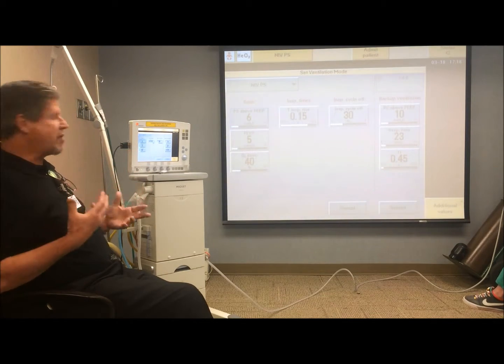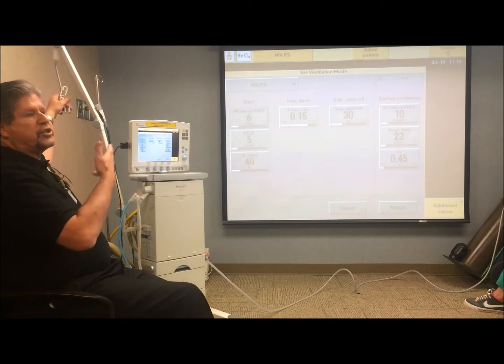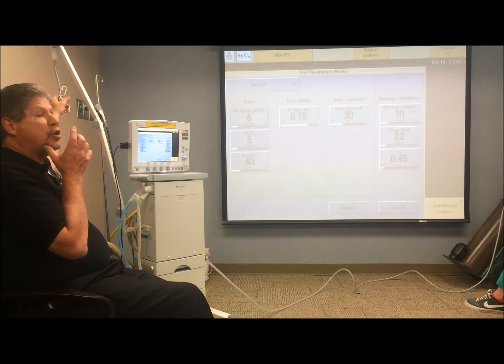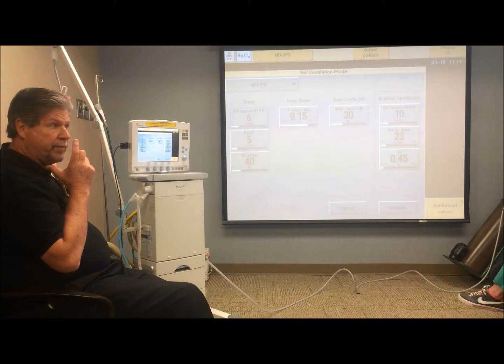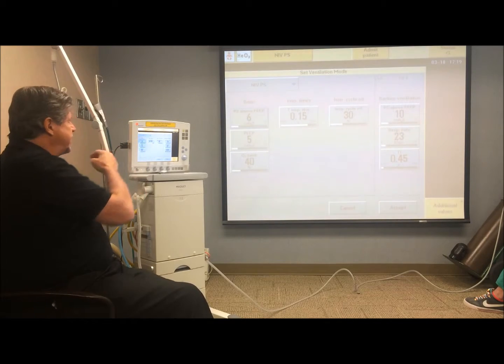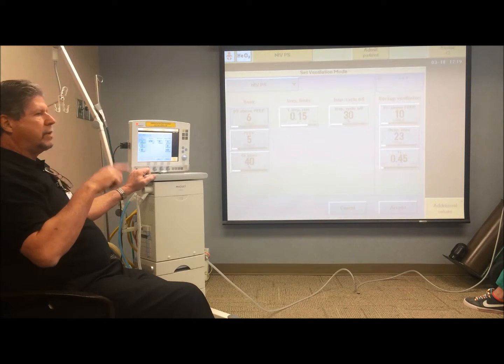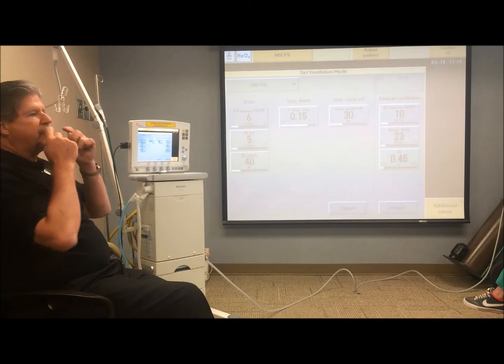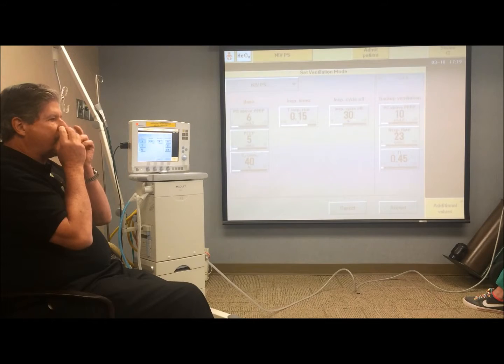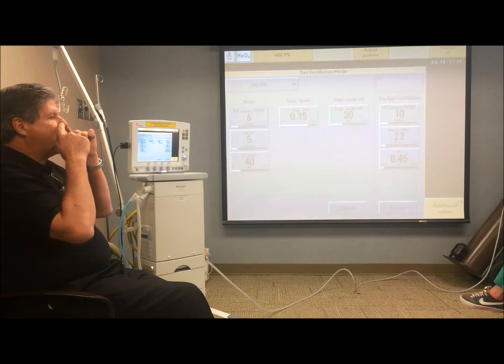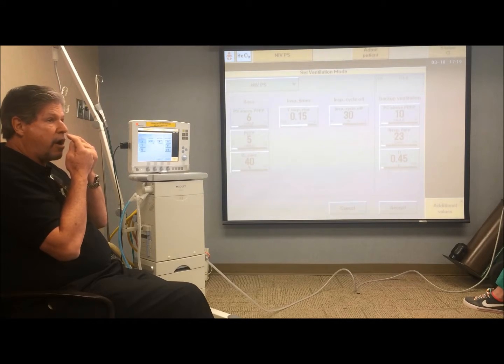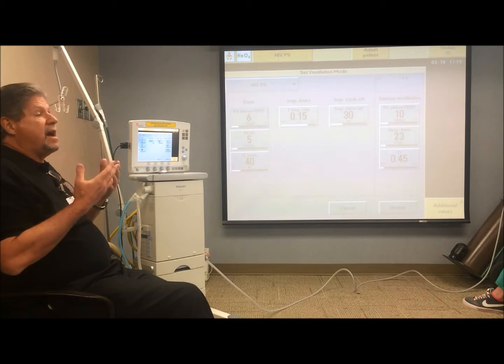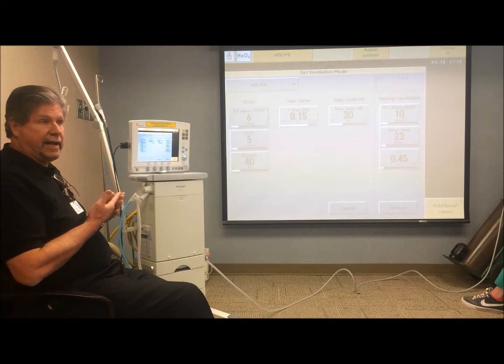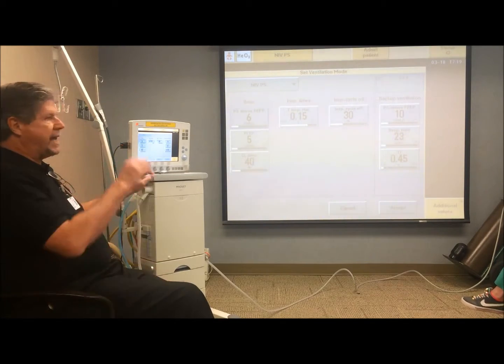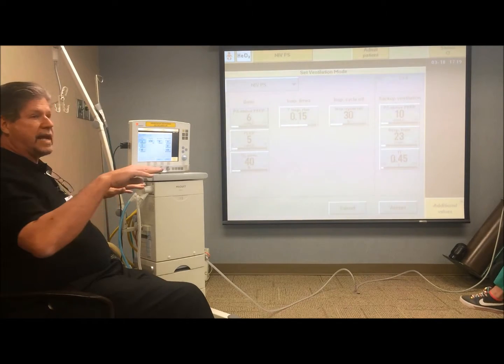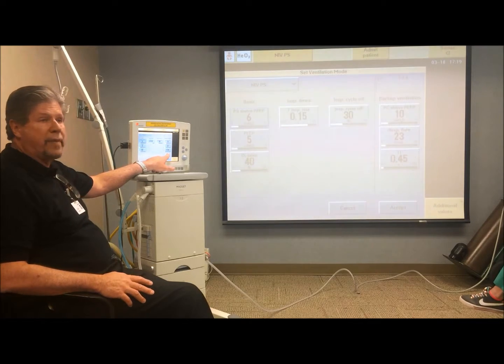They don't necessarily have the strength to trigger the ventilator in a traditional way like we would be able to if we had a closed or almost closed system with an endotracheal tube. So what happens is they started using this and they put the prongs in and they go, well, wait a minute, he's not triggering the ventilator. And he's not triggering the ventilator because the prongs that they were using were smaller than the nares, and when he breathed in through the nares, he was pulling air in through the space and not necessarily through the prongs, but if he did pull in through the prongs, it wasn't enough to trigger the ventilator even at the most sensitive setting. So what was happening is the ventilator would say, I don't detect any breaths, so after 10 seconds it would always go to backup.